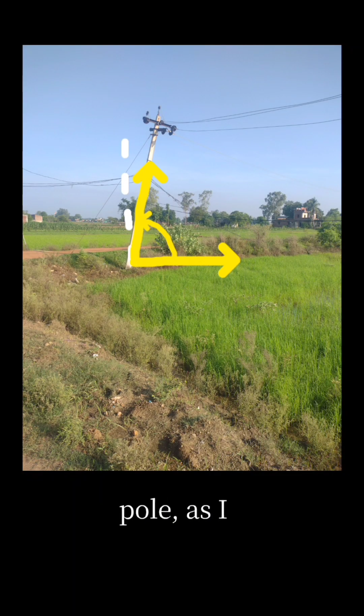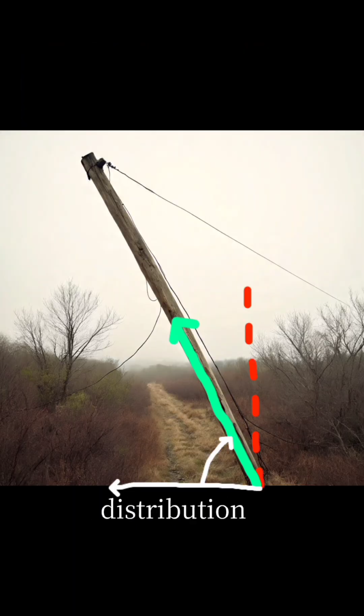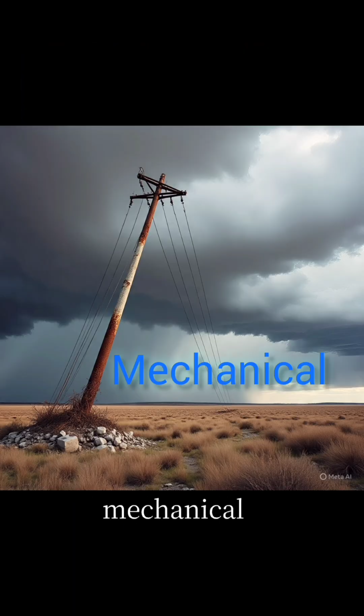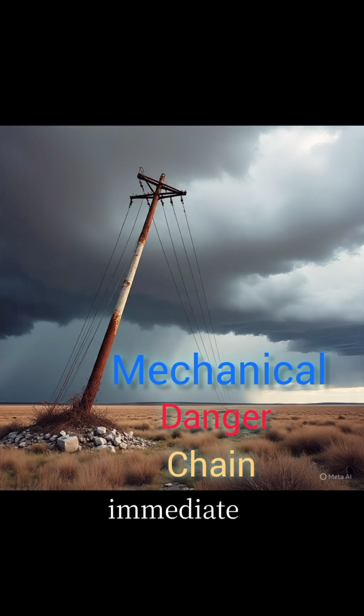I observed this tilted distribution pole in my locality. What might be the mechanical danger chain? Stage 1, immediate mechanical shift: uneven tension in the conductors. As the pole is tilted, uneven tension in the conductors is going to be created.